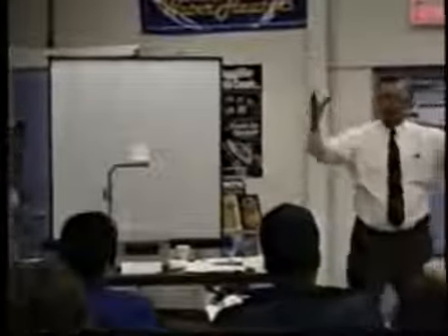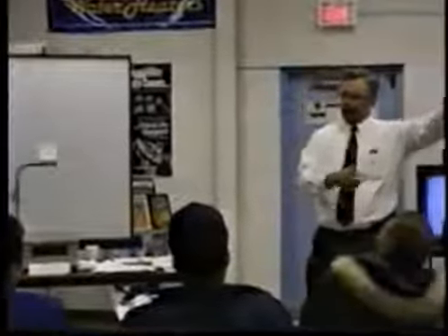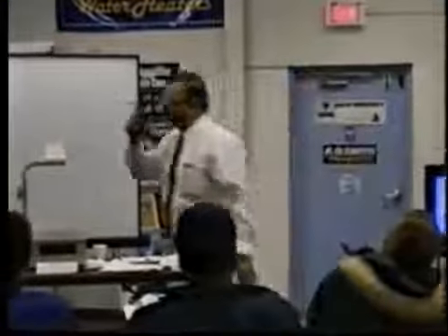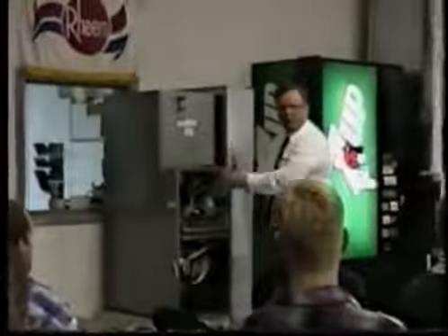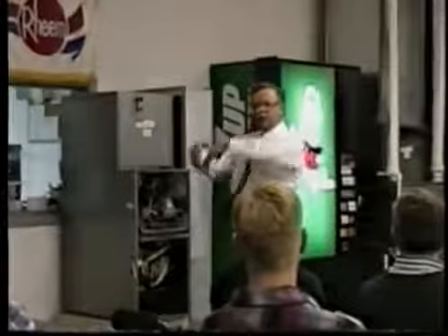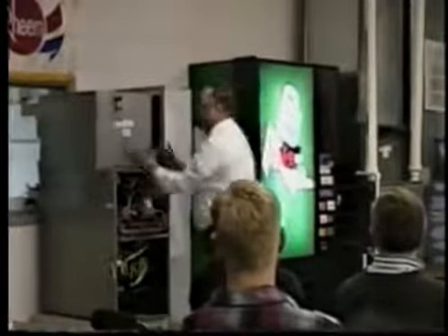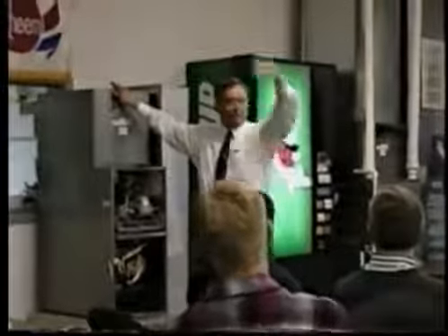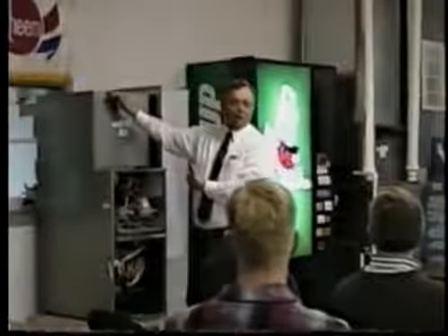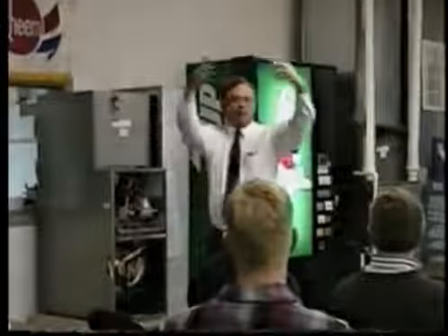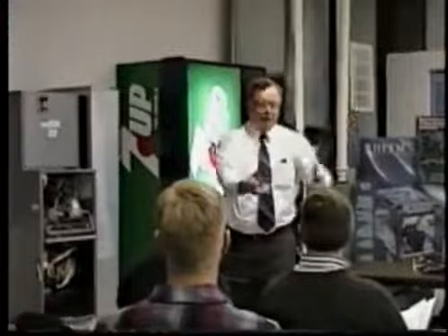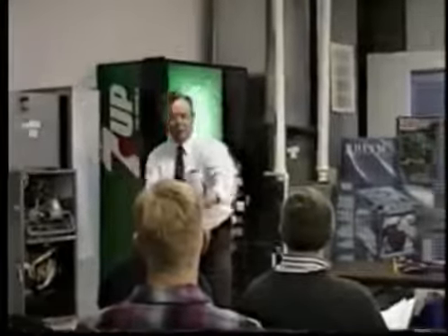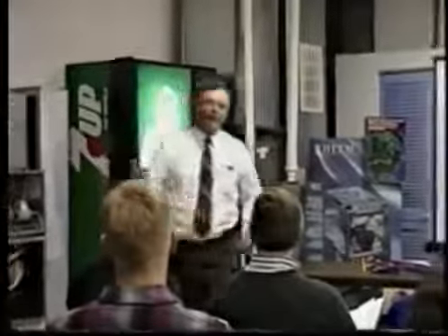And you have to know that in air conditioning, because heat moves from hot to cold. When we're in a home and we're trying to cool it, don't we take a lot of hot air? And right here, this would be an air conditioner in a home. If we take a lot of hot air and try to cool it, we have to run it through a coil that sits here, and the coil is cold. The coil's about 40 degrees, and maybe the air coming back to it is 100 degrees. So the air gives up its heat to the cold coil by running through the coil, and that's how we cool the air.